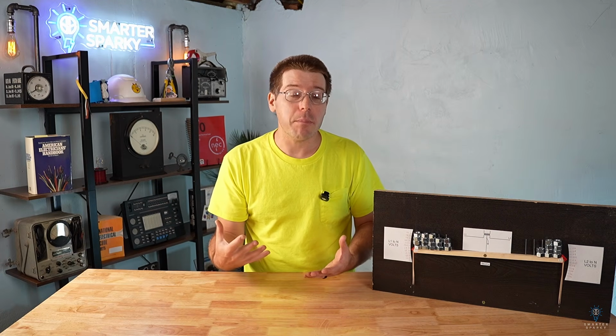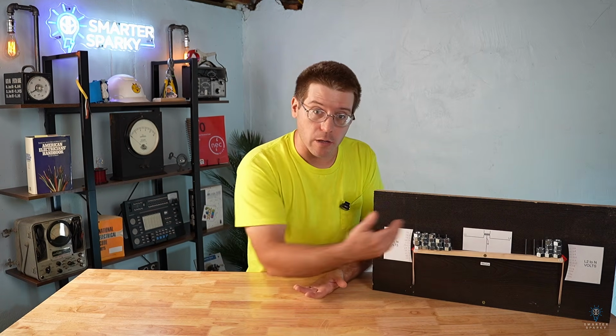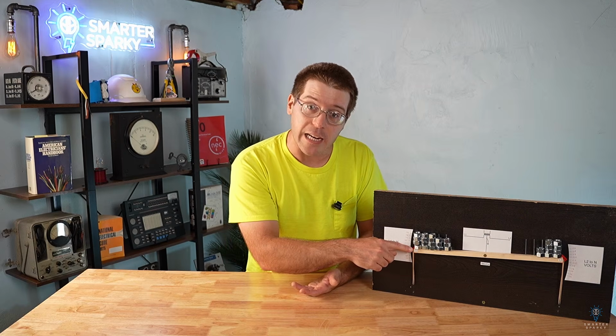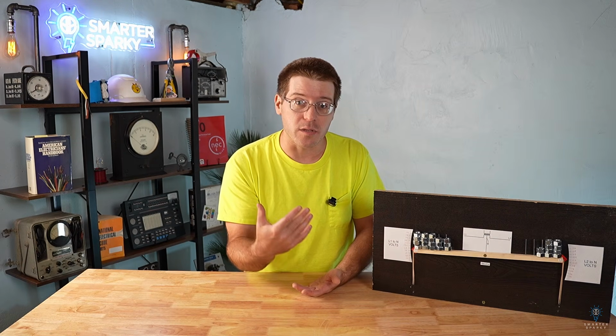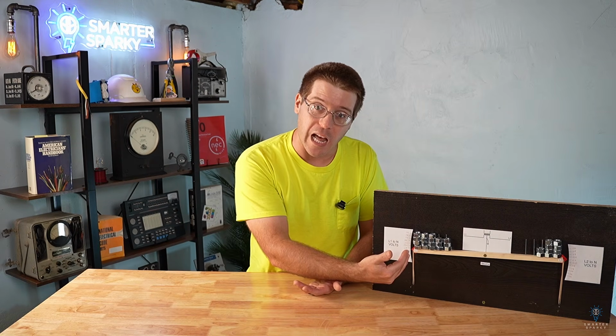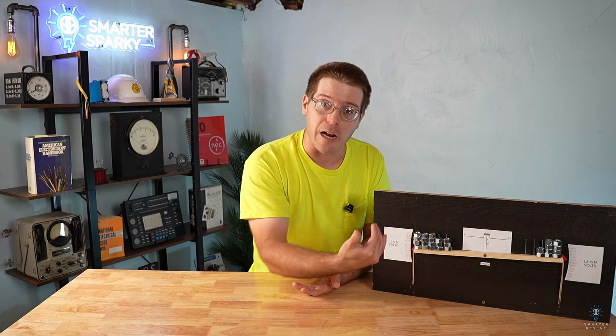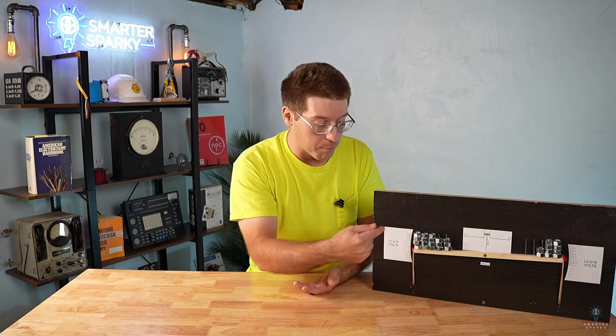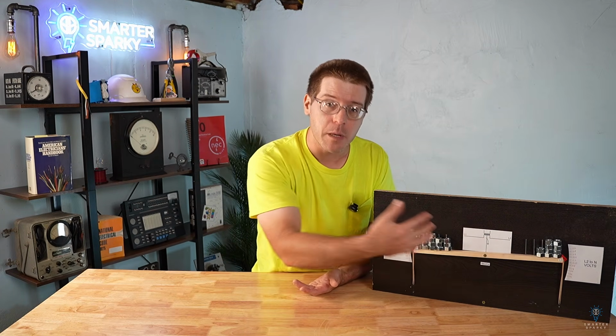There absolutely can be voltage issues on one particular line. Say, for example, one of the line lugs was loose. We could see those voltage drops on just one line, but because we were seeing it on both lines to neutral, but not from line to line, that triangulated us to that neutral being the issue.